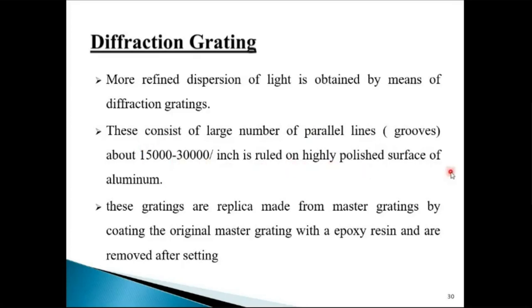These gratings are ruled on a highly polished surface of aluminium. These gratings are replicas made from a master grating by coating the original master grating with epoxy resin, and they are removed after setting. The original polished surface of aluminium with this density of lines is used; it is very difficult to produce.